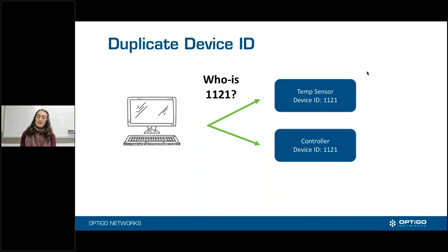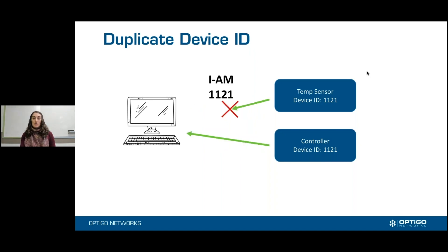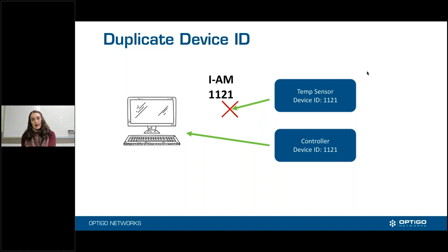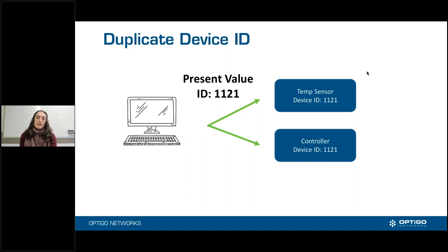But this is not forever. What's going to happen is the next time a who-is goes out, if the controller manages to get a message in first saying I'm 1121, then that device can be registered with the BMS as device 1121. So there's going to be some confusion because of that. It becomes a lot worse when it's looking for things like a present value.